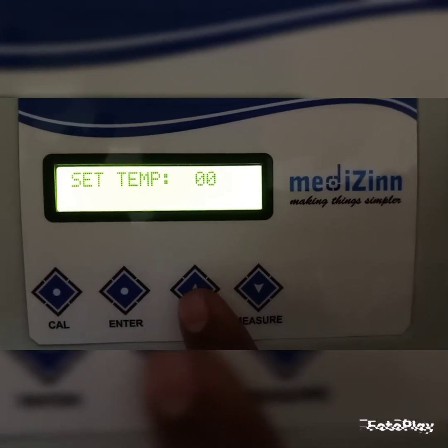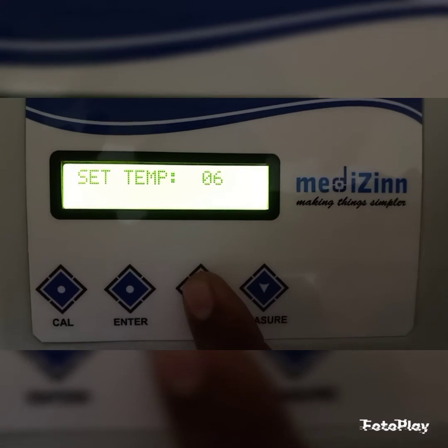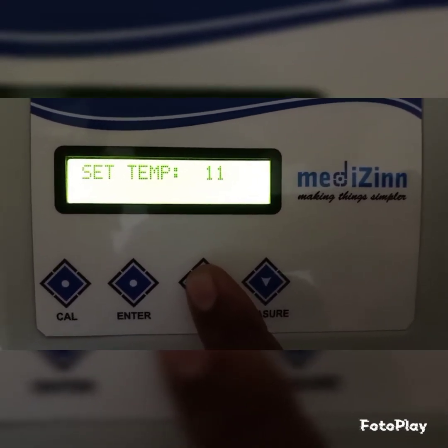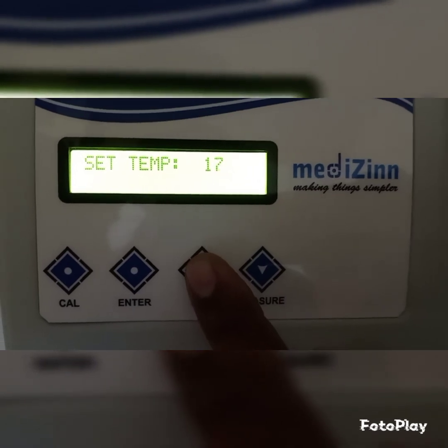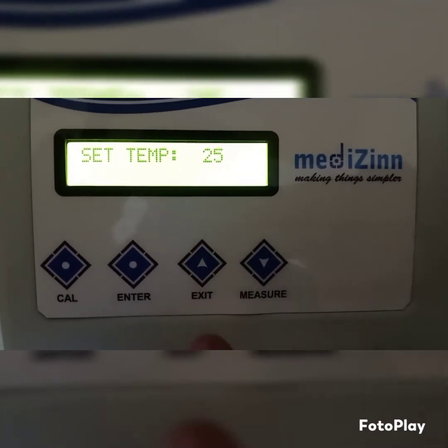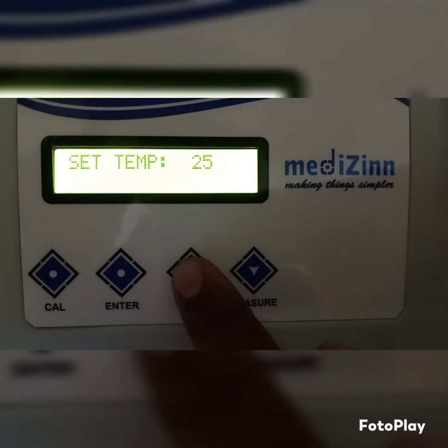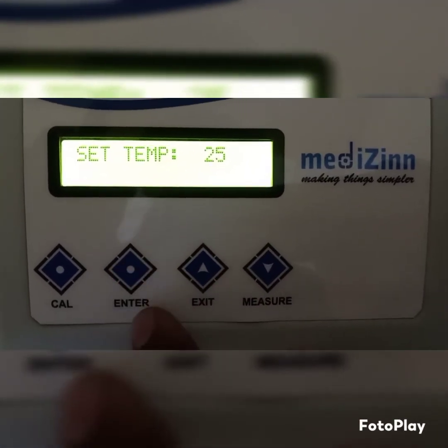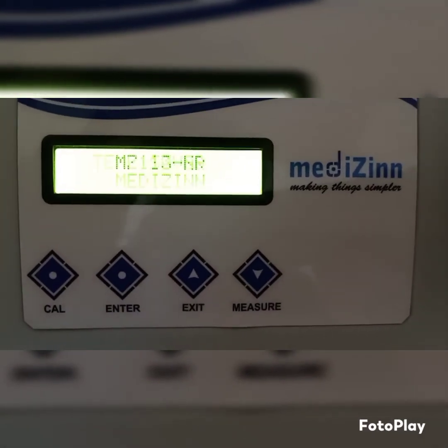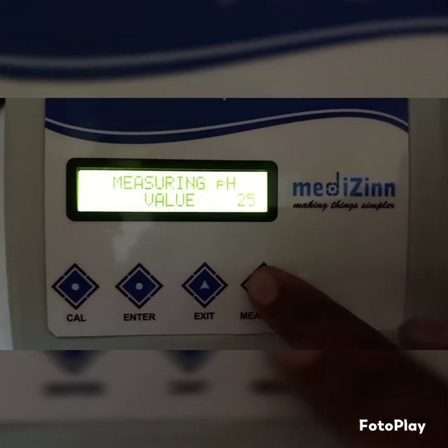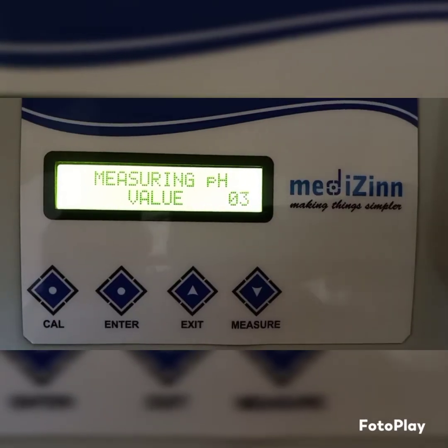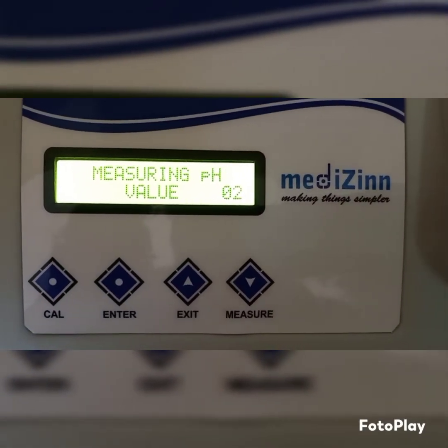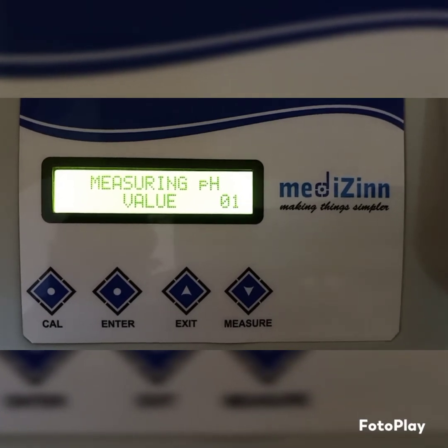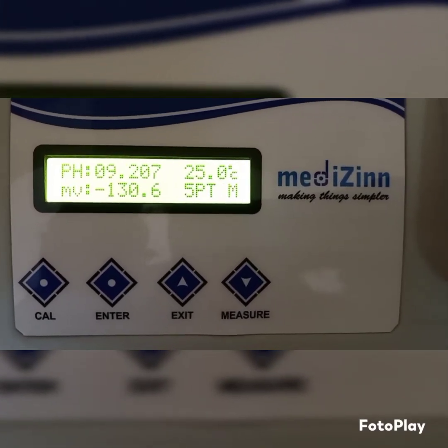So for the increment, press increment button. Suppose we want to go for 25 degree. Using increment and decrement button, make it 25, and after that press enter key to save the temperature. Now during the measurement process, instead of A, M will display. Now here M indicates that temperature is manual selected.